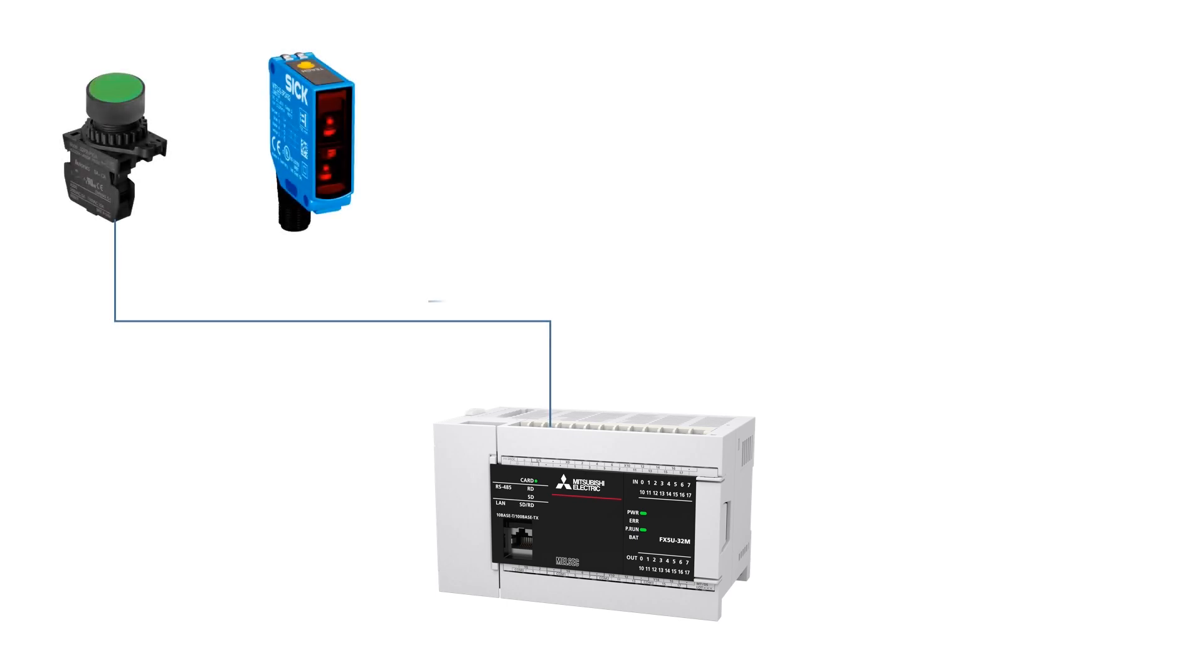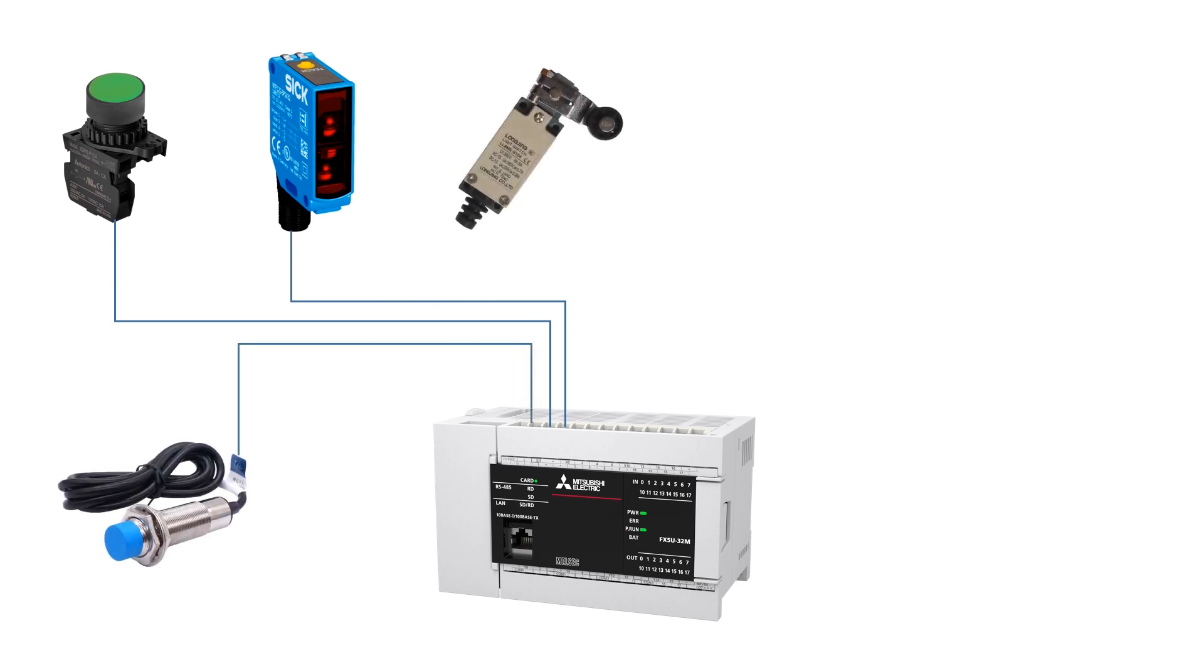PLC digital input signals represent two states, on and off. These signals are received from digital field devices such as push buttons, photoelectric sensors, proximity sensors, and limit switches. Simply put, a digital field input device acts as a normally open or closed contact, like a switch with on and off states.